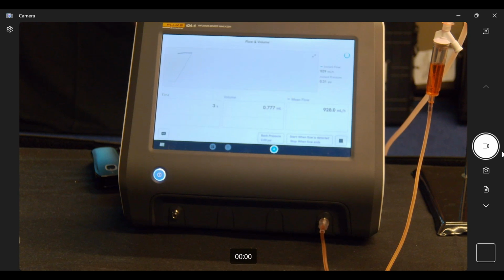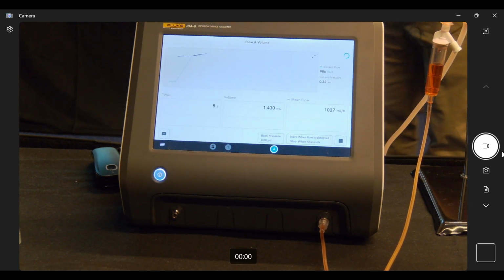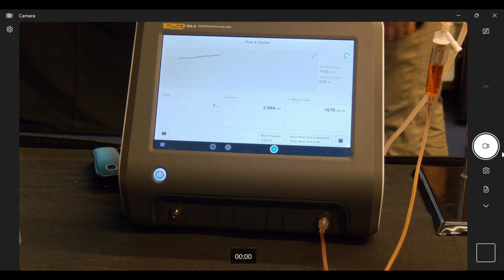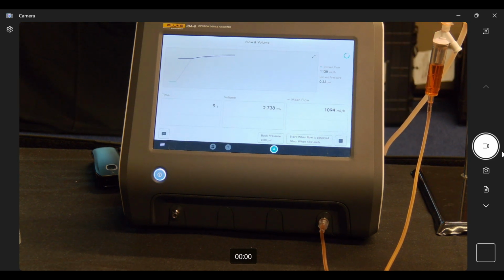You're going to know that my bag is free flowing, and I've established a flow rate and a volume. What the analyzer is doing is it wants to keep itself at atmospheric pressure at 0. So as it senses pressure on that stepper motor, it's trying to back it off, holding a perfect 0 for you. So with this analyzer pumping fluid back up the hill, we still maintain 0 pressure.